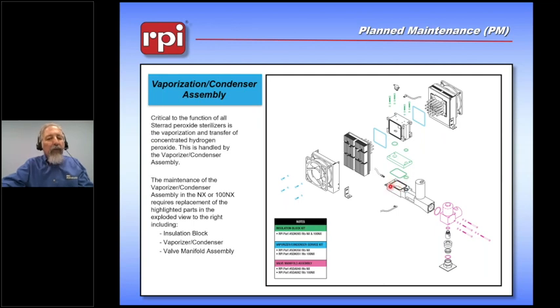Now, one of the problems we have heard about with this assembly is this. In this bottom area where the fluid is vaporized, it can develop salt deposits that are a byproduct of the processing system used to manufacture the hydrogen peroxide cartridges. There's also preservatives that are used within the hydrogen peroxide cartridge. There is also an insulator separating this subassembly from this subassembly, and that insulator will break down eventually with exposure to the hydrogen peroxide.